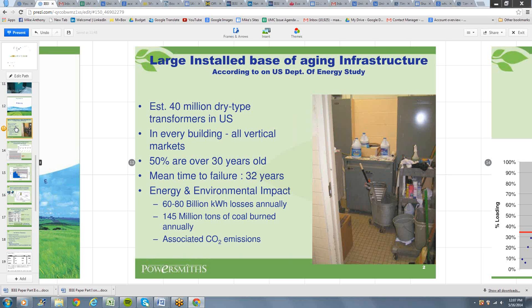The energy impact is substantial for these transformers, because while they're small and one might think insignificant, when you add those numbers up, we're talking 60 to 80 billion kilowatt hours a year, 145 million tons of coal burns just to feed those wasted watts that are coming off as heat in the transformer. So carbon footprint contribution. So it's grid capacity and cost. So a pretty big deal for something that really doesn't get much thought.